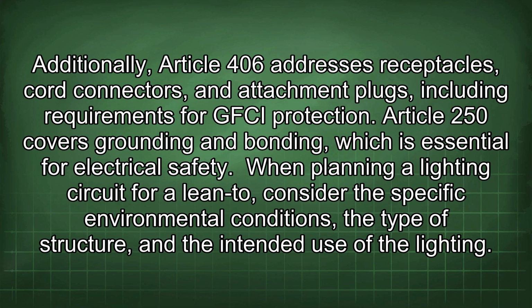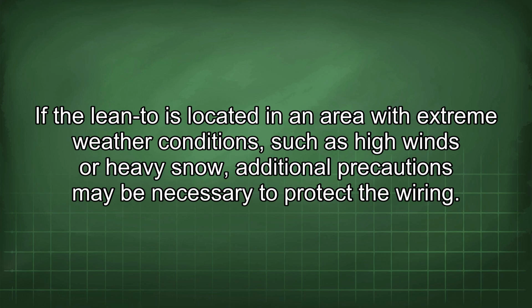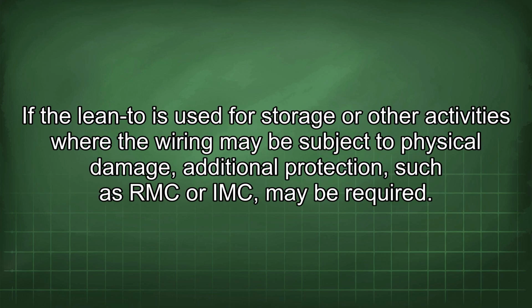When planning a lighting circuit for a lean-to, consider the specific environmental conditions, the type of structure, and the intended use of the lighting. If the lean-to is located in an area with extreme weather conditions such as high winds or heavy snow, additional precautions may be necessary to protect the wiring. If the lean-to is used for storage or other activities where the wiring may be subject to physical damage, additional protection, such as RMC or IMC, may be required.